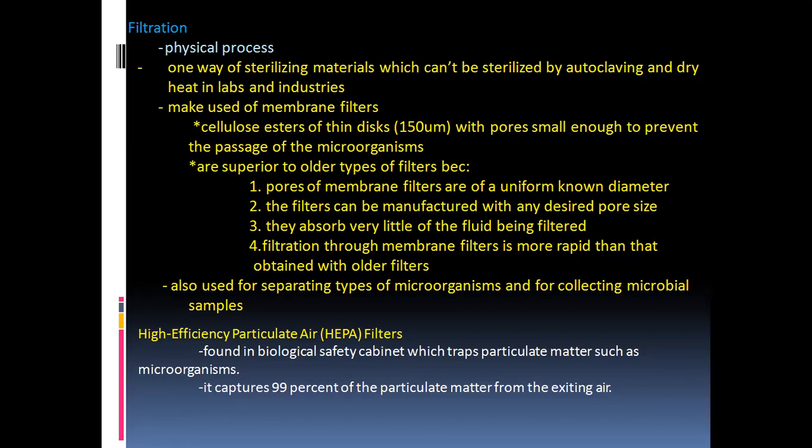Efficiency is very high for the high efficiency particulate air filters, HEPA filters, which are installed at the entrance of various rooms, like in research labs and in hospitals. So these also filter the air. These HEPA filters are found in the biological safety cabinet, which traps particulate matter such as microorganisms. It captures 99% of the particulate matter from the exiting air.